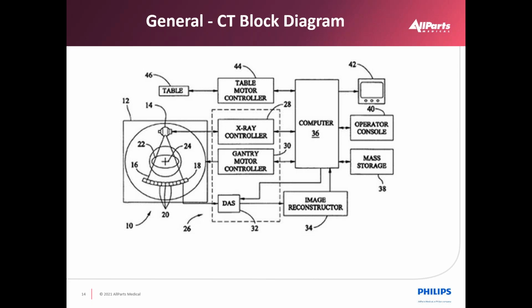Okay. So as we move over, we see the X-ray controller. We call that the X-ray generator nowadays in CT, and X-ray rooms call it the X-ray generator as well. It works in conjunction with providing high voltage DC to the X-ray tube and filament control. Think about a conventional light bulb where the filament lights up: we control the temperature, or the amount of electrons produced by that filament heating. That's called mA control. We control that with the X-ray generator, and we deal with high voltage.